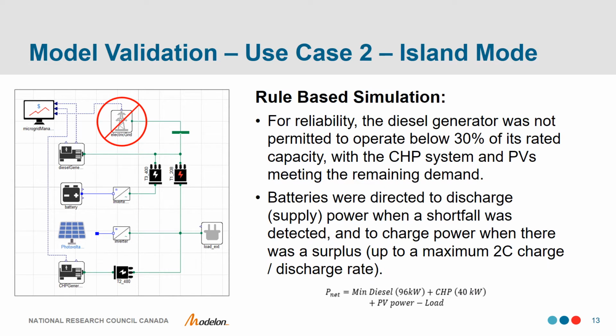Now that we've shown that the results of our diesel-only simulation are reasonable with respect to real-world results, we can move on to use case 2, where we're adding renewables and energy storage to the microgrid. For reliability, the diesel generator was not permitted to operate below 30% of its rated capacity, with the CHP system and PV output meeting the remaining demand. Batteries were directed to discharge power when a shortfall was detected and to charge power when there was a surplus, up to a maximum of a 2C charge or discharge rate.